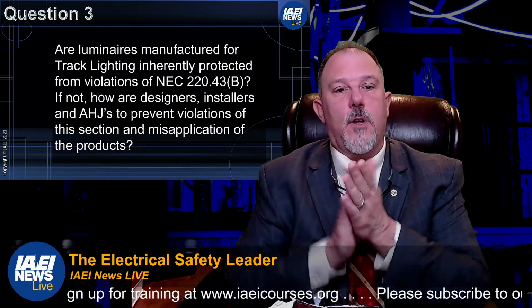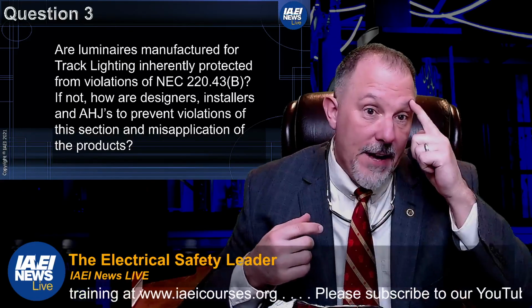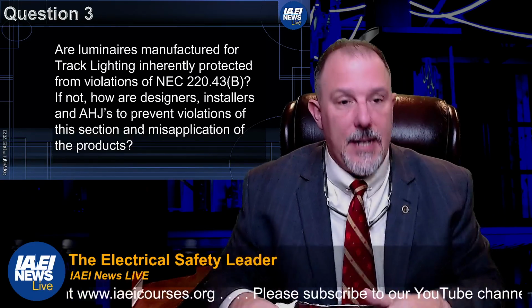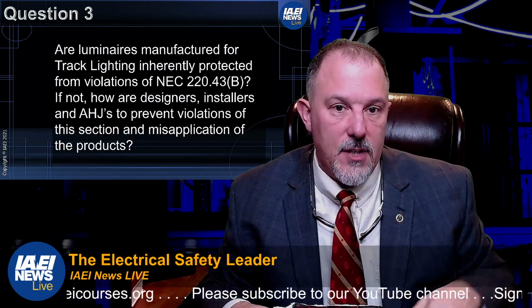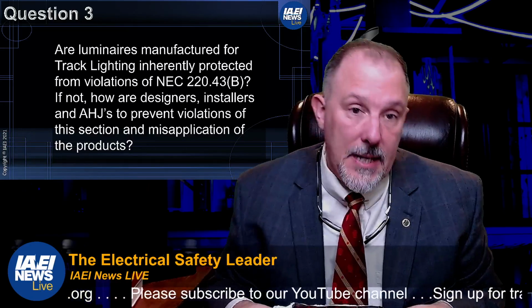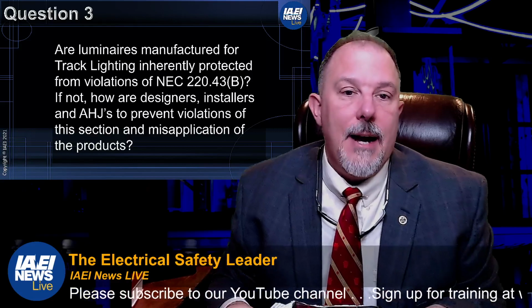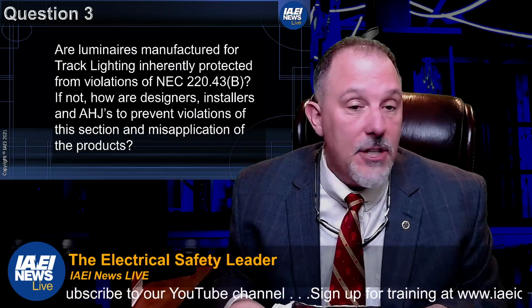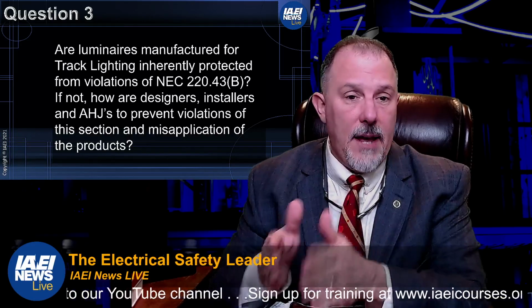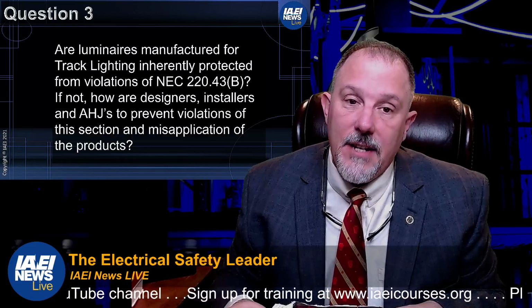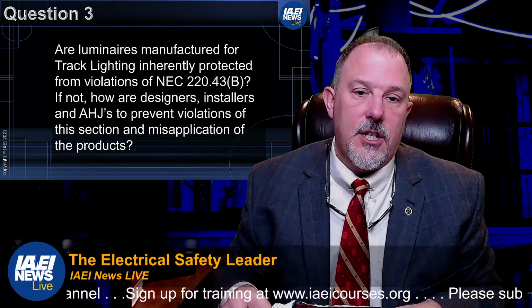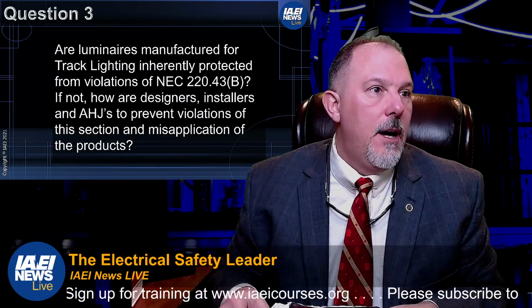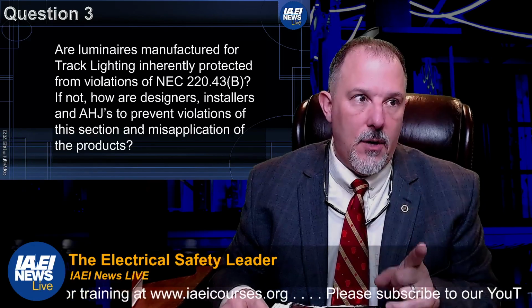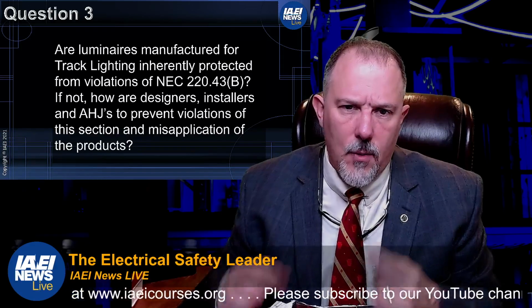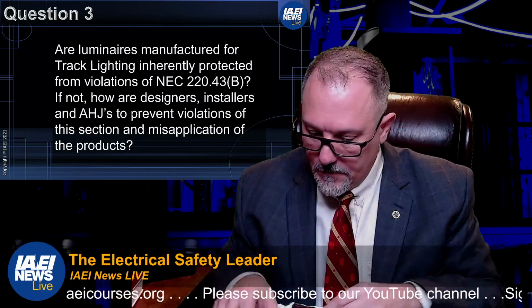All right. Are luminaires manufactured for track lighting inherently protected from violations of NEC 220.43(B)? If not, how are designers, installers, and AHJ, remember, that is authority having jurisdiction, to prevent violations of this section and misapplication of the products? So the first thing we've got to do, 220.43(B).